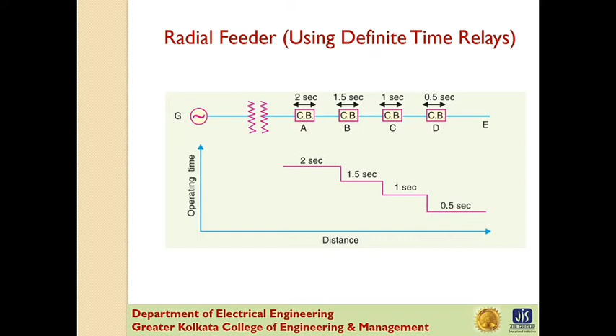If the relay at D fails to trip, then the relay at C will operate after 0.5 second, that is, after 1 second from occurrence of the fault. The disadvantage of this scheme is that if there are a number of feeders in series, the tripping time for faults near the supply end becomes high. In this case it is 2 seconds. The operating time of relay A, which is near to the supply, is 2 seconds. However, in most cases it is necessary to limit the maximum tripping time to 2 seconds. Now these disadvantages can be overcome to a reasonable extent by using inverse type relay.